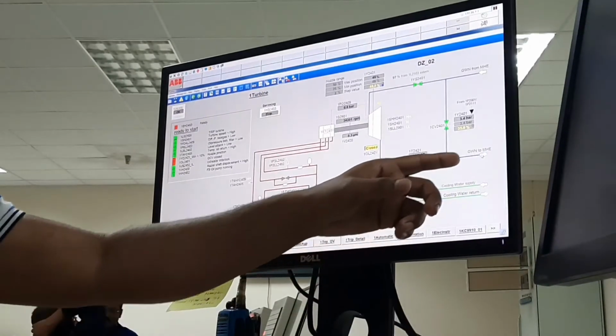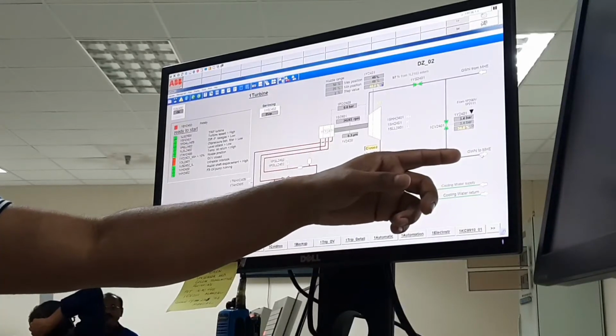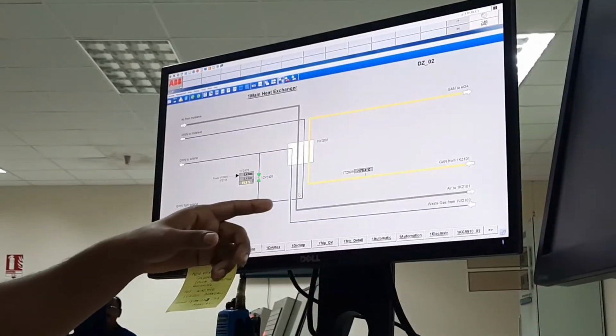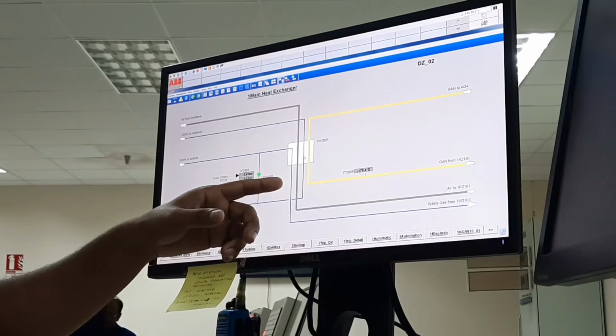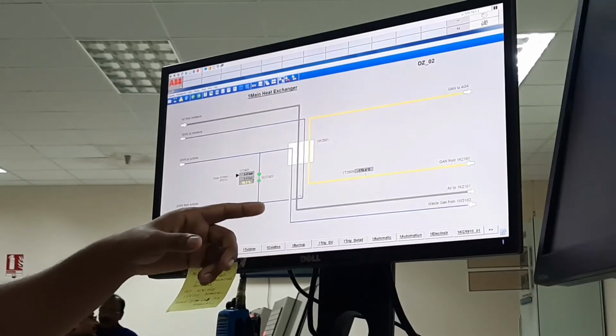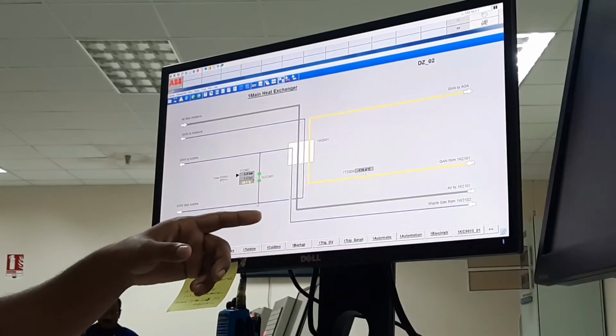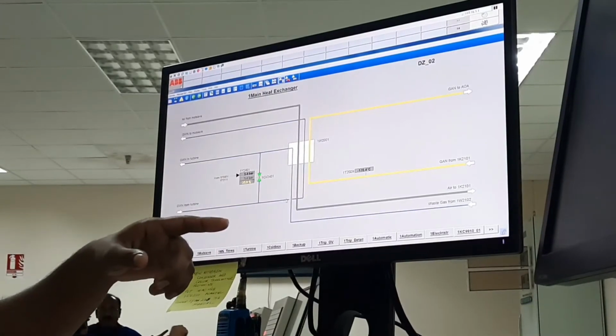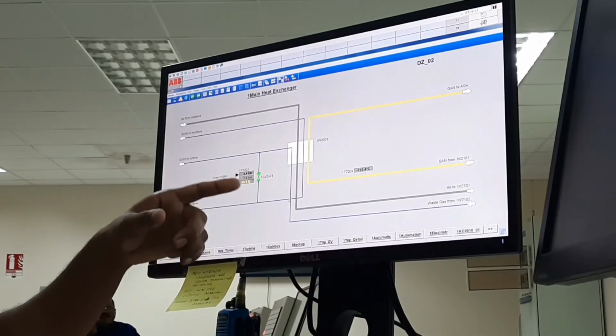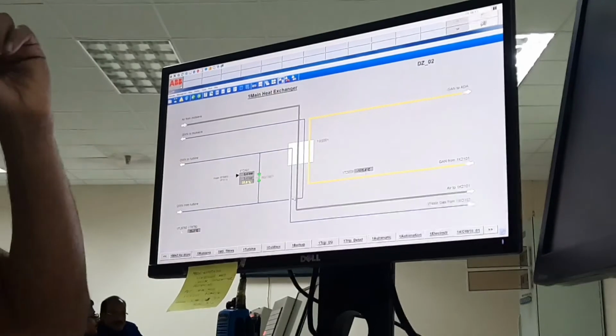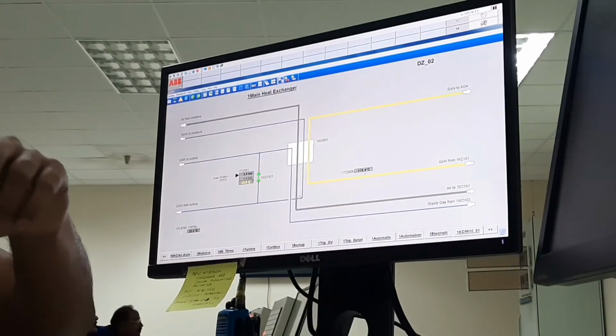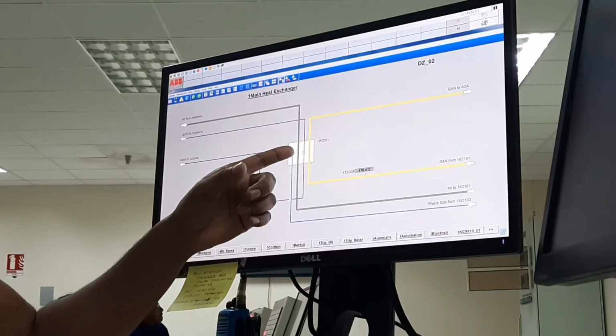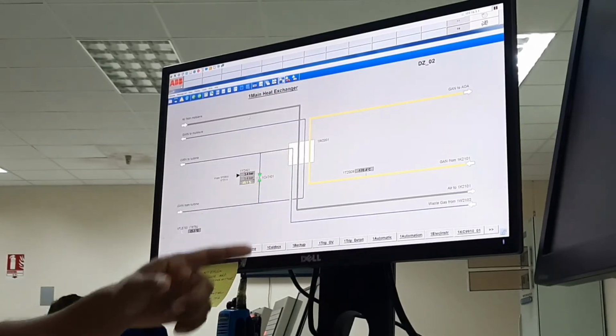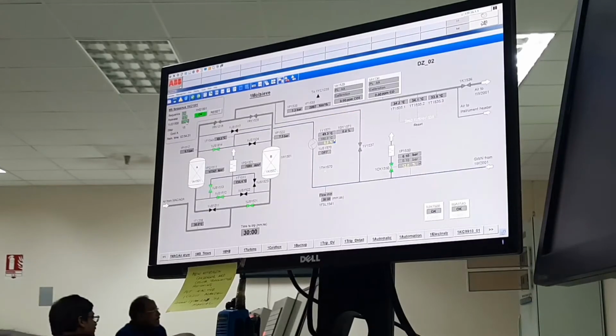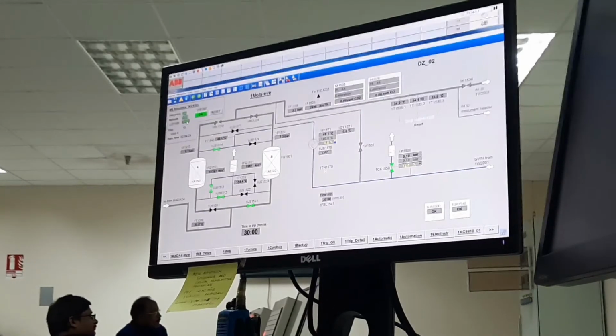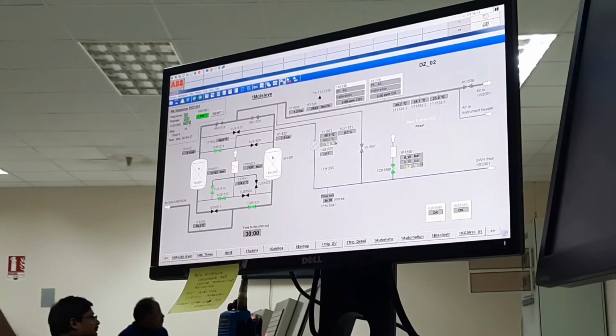After that it will go again to the main heat exchanger. Again this will go to the main heat exchanger. The pressure on this side is 0.35 kg and the temperature is minus 180 degrees centigrade. This 2000 normal meter cube flow per hour will go through the main heat exchanger, then directly to the molecular sieve unit for regeneration, and after it will go directly to the atmosphere.